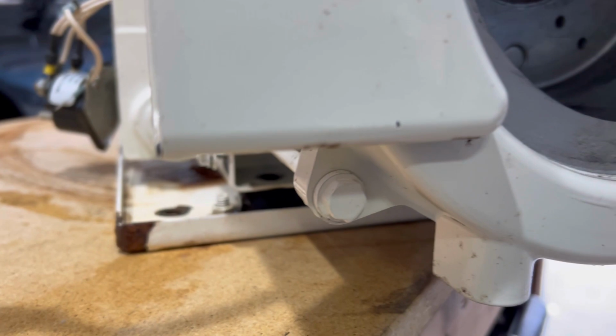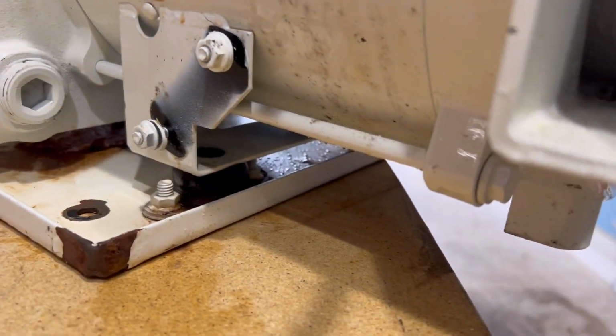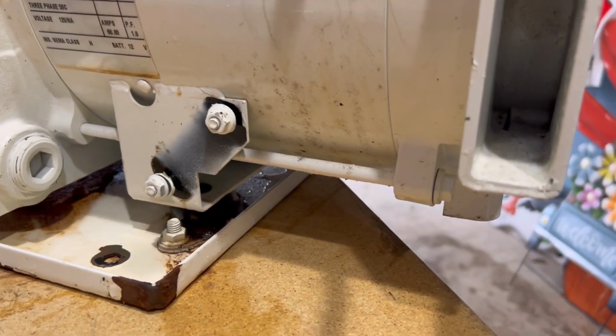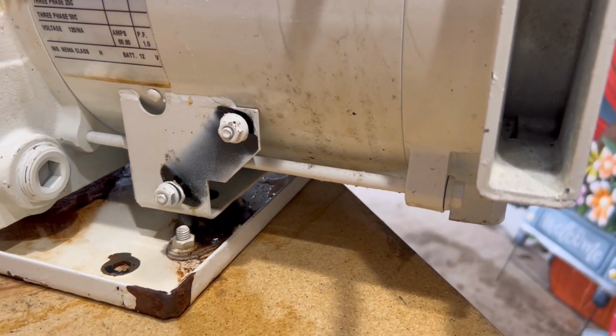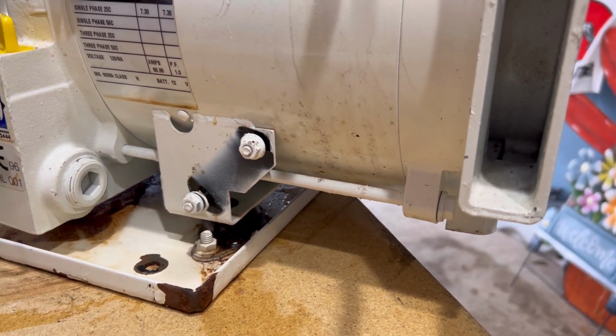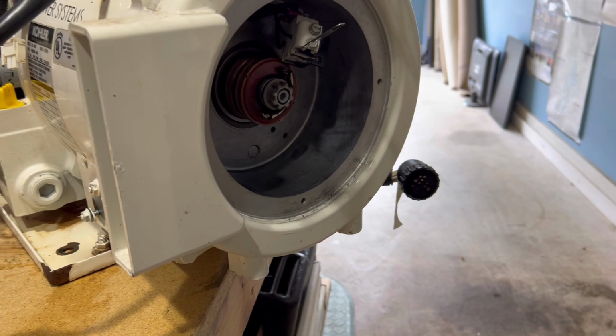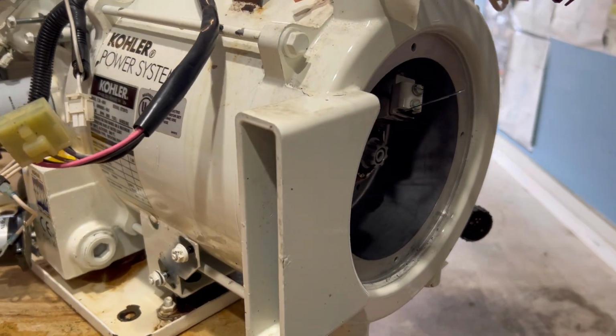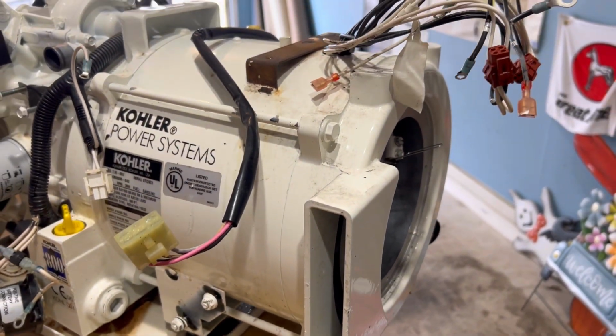Removing that nut from the top will allow us to lift up this end of the generator, per the service manual, to begin loosening the long cover bolts. We'll start this process next and see if hopefully this whole housing will come off together, and we may not need to remove the leads.